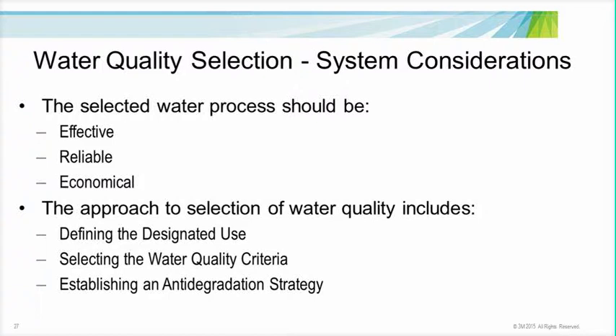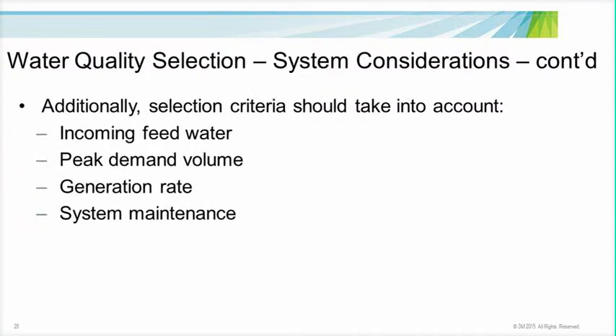Next, the water quality criteria should be selected for monitoring. Common quality criteria measurements are microbial, total organic carbon, or conductivity. And finally, establishing these anti-degradation strategies maintain the longevity of the system. Proper design and operational performance is used to minimize biofilm formation and system fouling, for example. Water selection criteria should take into account incoming feed water impurities such as total dissolved solids, peak demand volumes for proper sizing of filtration system and storage tank, and system maintenance. Installing a complex system without proper know-how of maintenance requirements may lead to out-of-spec conditions and expensive repairs leading to excessive downtime. These user needs factor directly into system design and configuration.